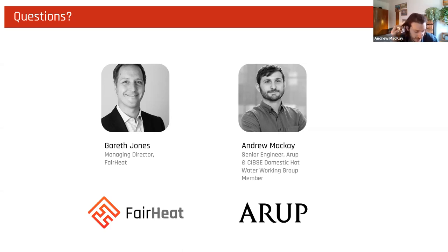So although the view of HSE is that an HIU in a typical application is a low volume system, and therefore it doesn't require you to check your temperature at any particular temperature, we just feel that 50 degrees is the right position in terms of giving maximum functionality and maximum safety. I've got Marco Kosic in my ear at the moment. I can hear him say, in reality, there is nothing stopping you from setting 45 degrees. I think as an industry, we've coalesced around 50 degrees.